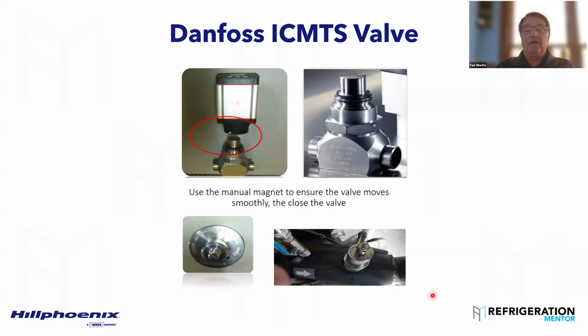And one of the things I'd like to see, especially at startup, is you have to pull that valve off. If you don't, you're not doing something right, because you have to pull it off. You got to work that valve, make sure that it doesn't stick. It's nice, smooth, and it's a very smooth turning device because it's magnetically coupled to the bonnet of that valve, and that's how it turns the internal mechanism.